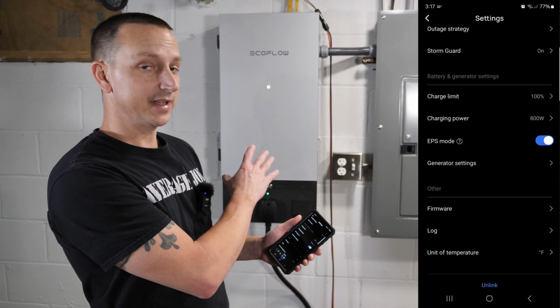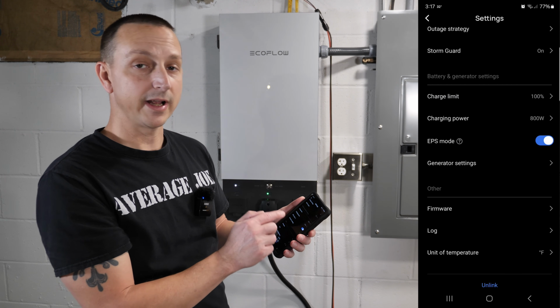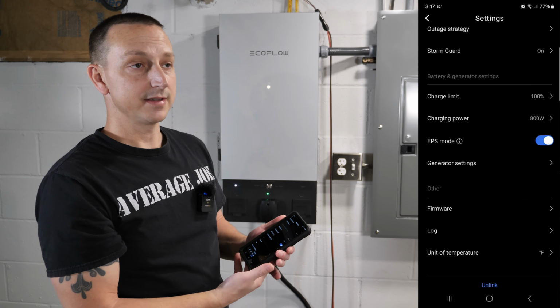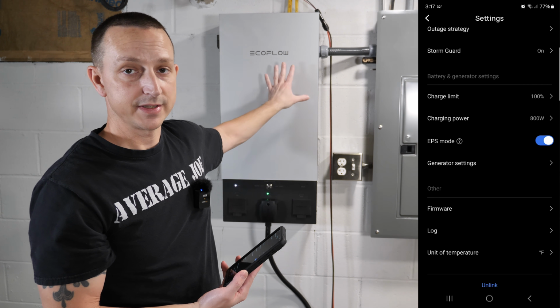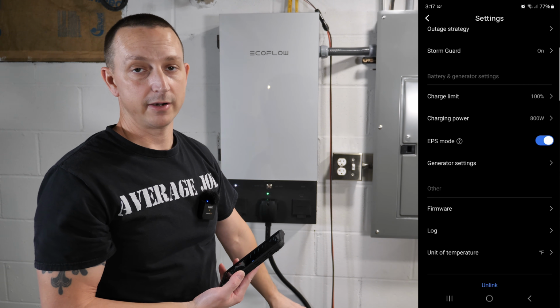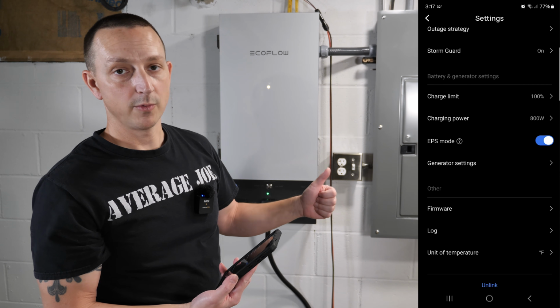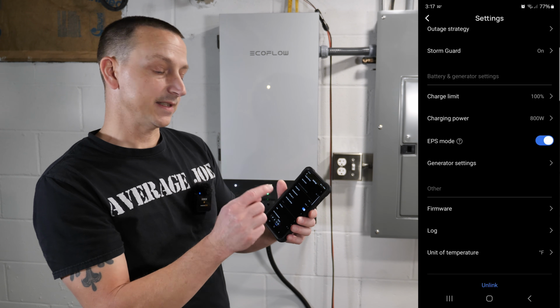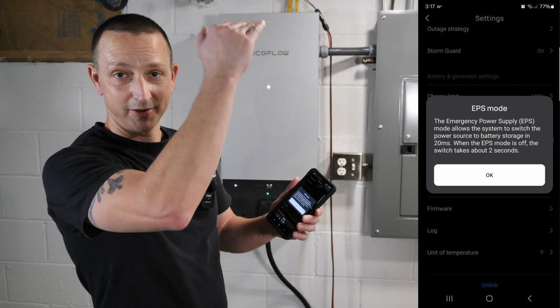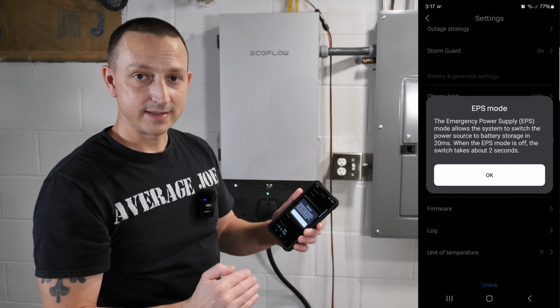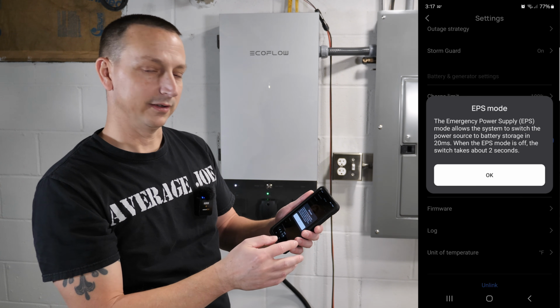EPS mode, if you're using this for a UPS, basically you want to have that enabled. What that means is if the grid goes down, this is going to automatically switch over to the battery and the inverter within that 20 millisecond time. If that switch is not enabled, basically your house is going to shut down for a couple of seconds and then repower up. I learned that already.